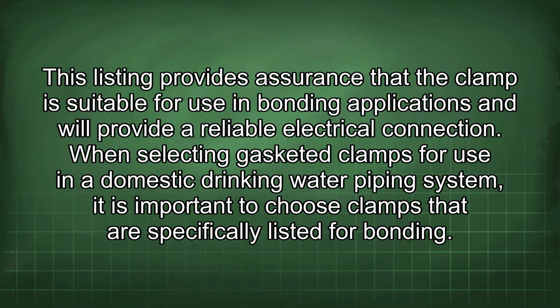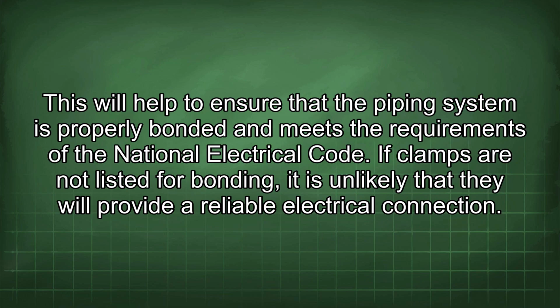When selecting gasketed clamps for use in a domestic drinking water piping system, it is important to choose clamps that are specifically listed for bonding. This will help to ensure that the piping system is properly bonded and meets the requirements of the National Electrical Code. If clamps are not listed for bonding, it is unlikely that they will provide a reliable electrical connection.